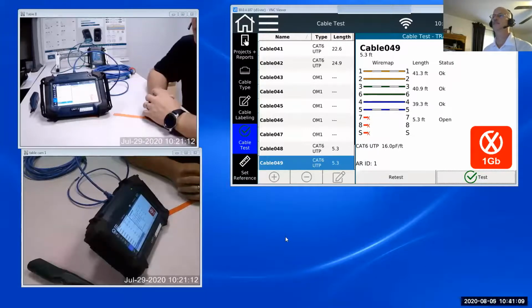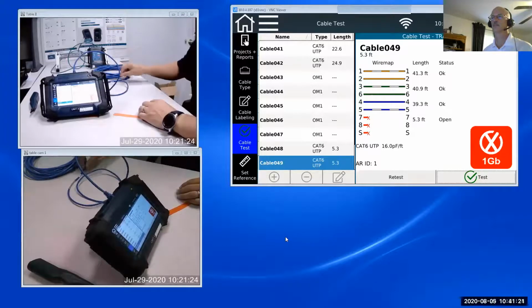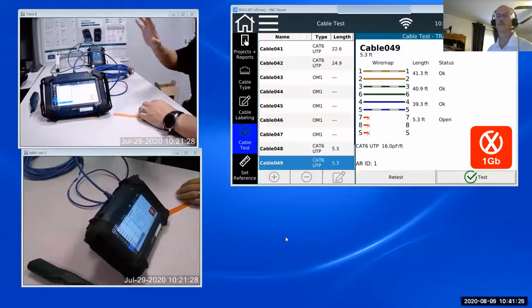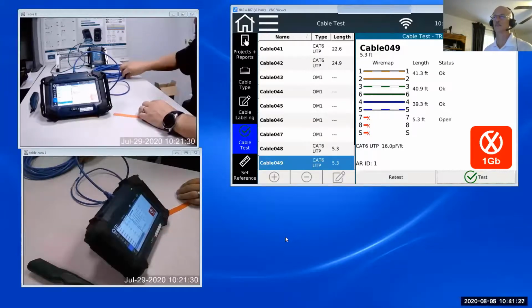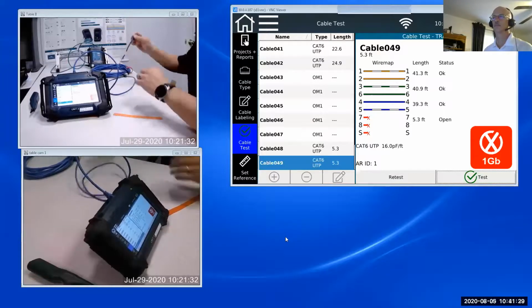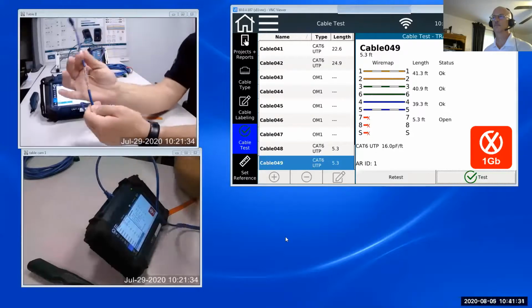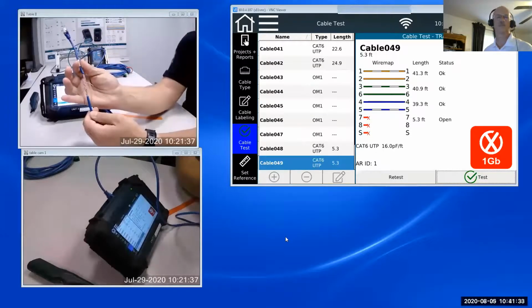Where do we have a problem with 7-8? The overall length of the cable is around 40 feet — we can see that. But pair 7-8 is only coming in at 5.3, or 5 feet. That's telling us that there is an open in this first segment of the cable. So we'll just take a look at that, and sure enough, you can see here we have an open on that 7-8 pair.